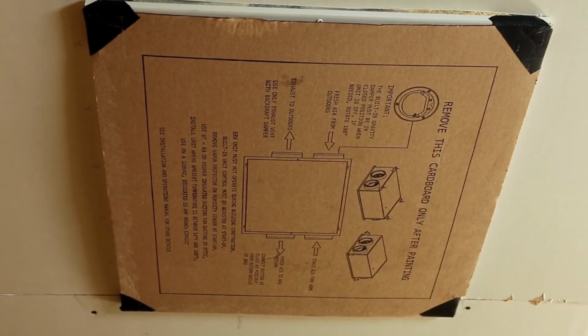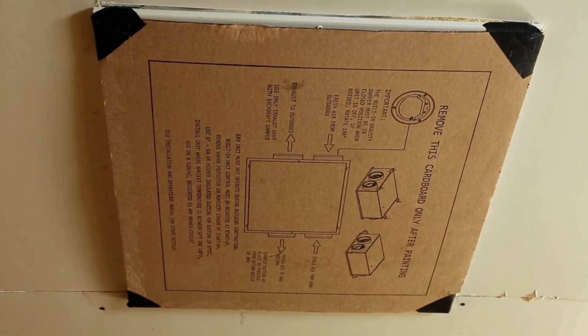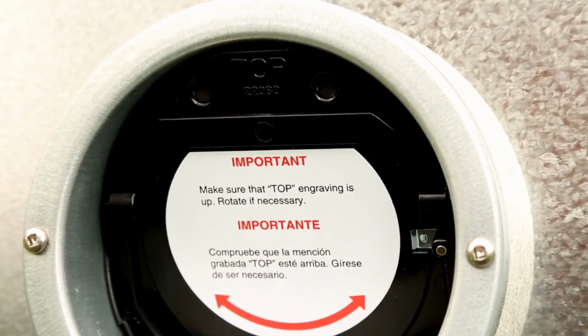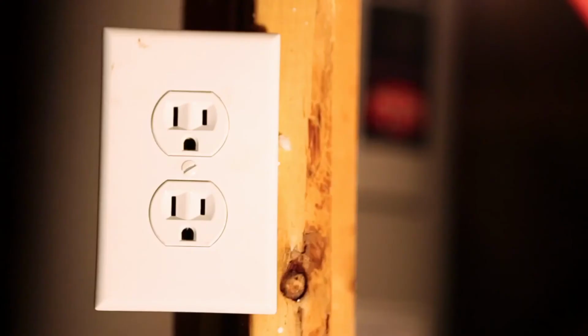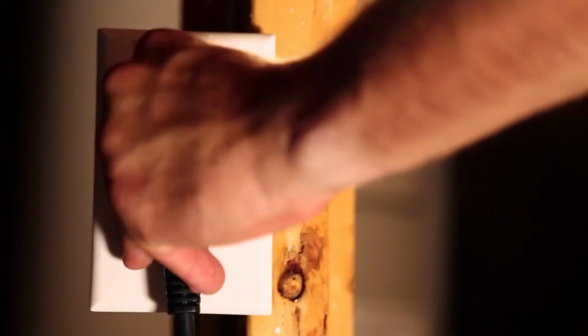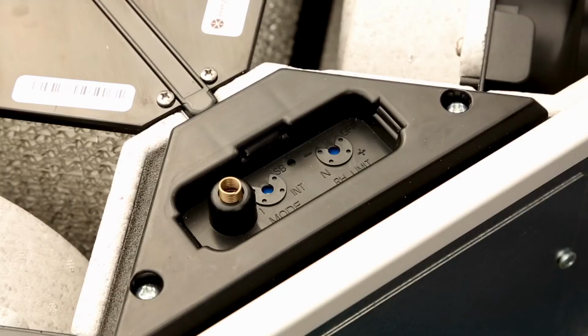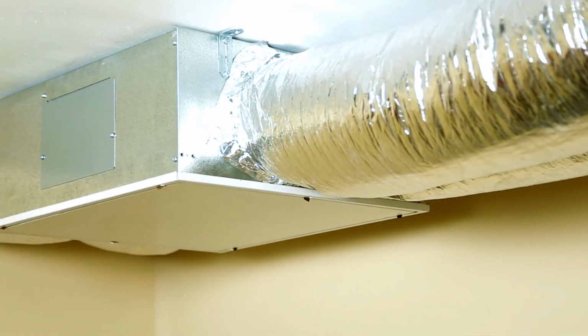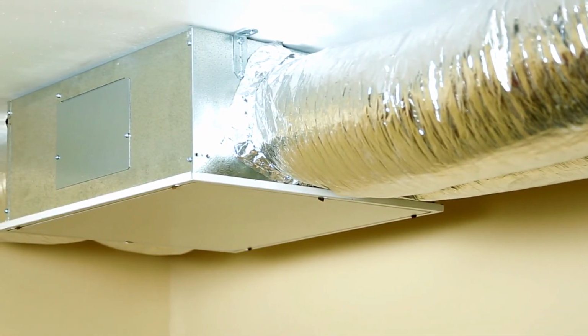Before starting the unit, remove the protective cardboard from the door if you haven't already, and verify the damper orientation. When the unit is powered on, it will go through a booting sequence. If there's a problem, the LED light will blink. Fast blinking indicates a motor problem. Slow blinking indicates a problem with the RH or temperature sensor. The ERVS100 is now installed and ready for use.